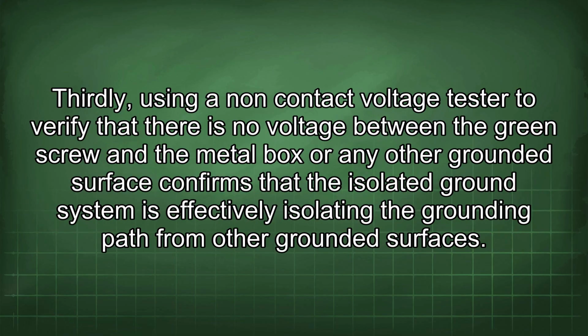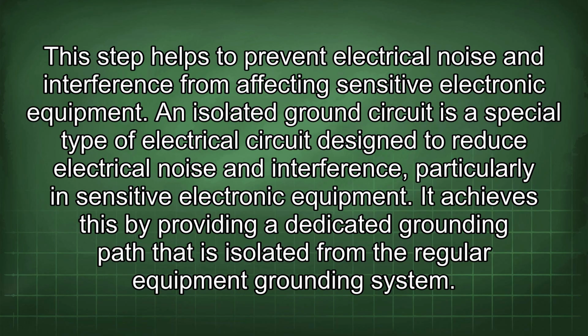Thirdly, using a non-contact voltage tester to verify that there is no voltage between the green screw and the metal box or any other grounded surface confirms that the isolated ground system is effectively isolating the grounding path from other grounded surfaces. This step helps to prevent electrical noise and interference from affecting sensitive electronic equipment.